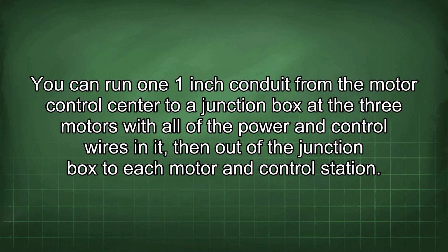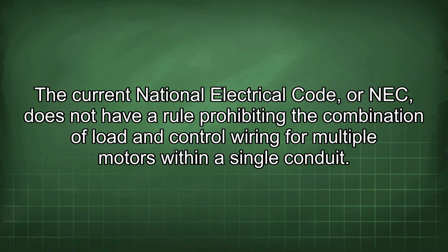You can run one 1-inch conduit from the motor control center to a junction box at the 3 motors with all of the power and control wires in it, then out of the junction box to each motor and control station. The current National Electrical Code, or NEC, does not have a rule prohibiting the combination of load and control wiring for multiple motors within a single conduit.